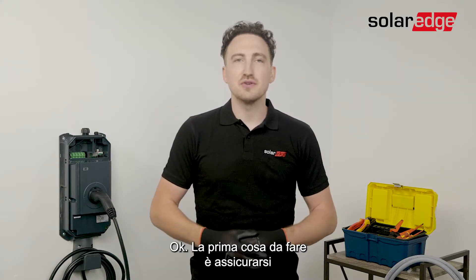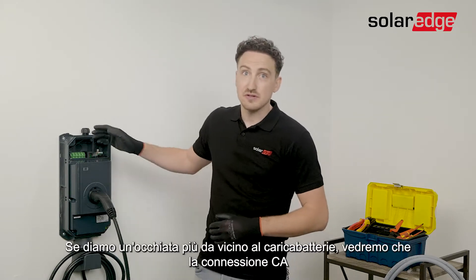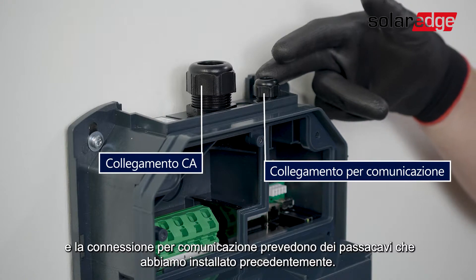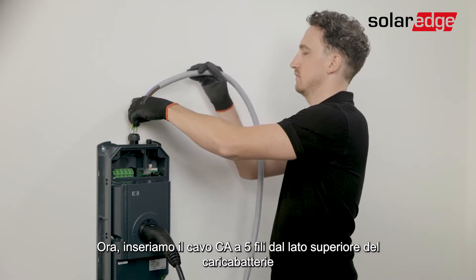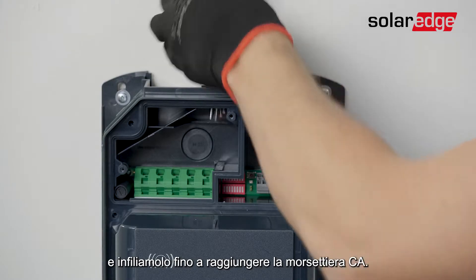First thing you want to do is make sure that the AC power is switched off. If we have a closer look at the EV Charger you'll see that the AC connection as well as the communication connections already have their cable glands, which we have installed in advance. Now you need to insert the AC cable through the top of the SolarEdge EV Charger and pass them through until they reach the AC terminal block.